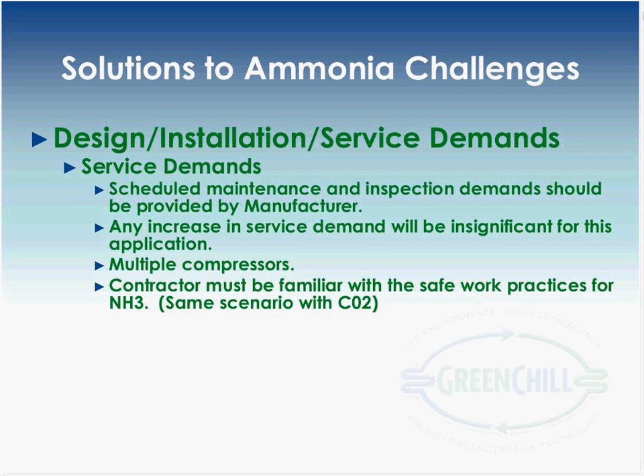And then as far as the compressors go, we're still going to have multiple compressors. So service on compressors would be the same, in that you can isolate a compressor without having to shut down the store or the entire system to do maintenance. Some systems do use very large screw compressors, with one compressor for the whole system, and that's a little different story, but we would still probably be looking at using multiple compressors. And the biggest thing is just the contractor becoming familiar with the safe work practices for ammonia. And like I said, that's the same scenario as CO2.